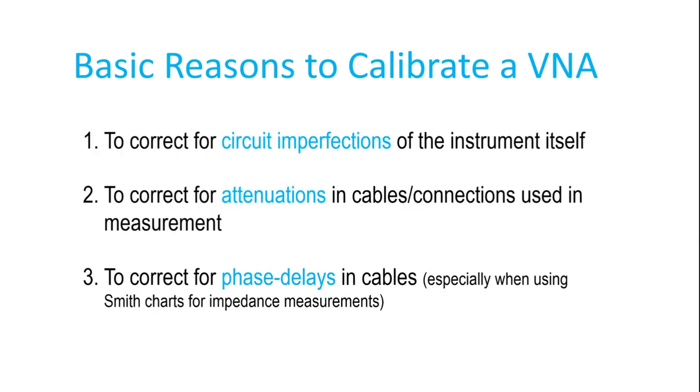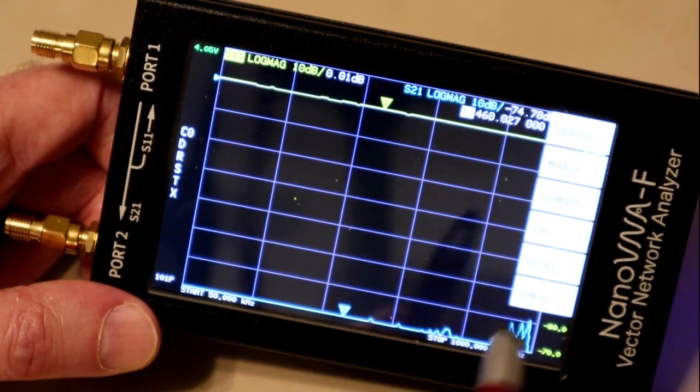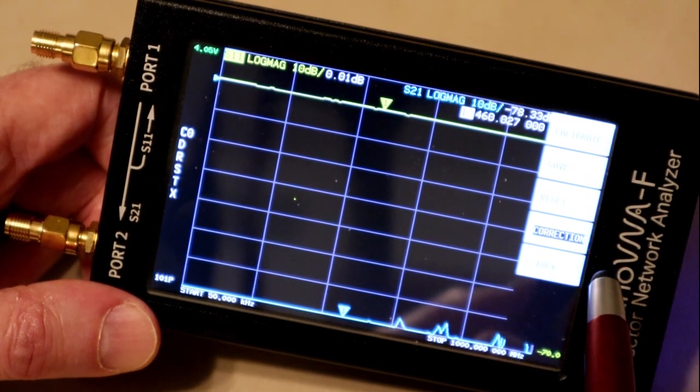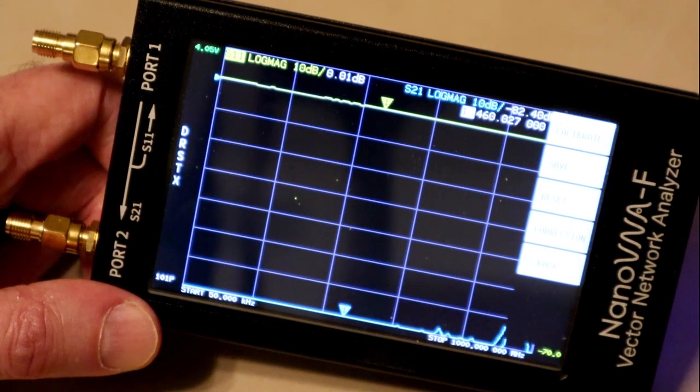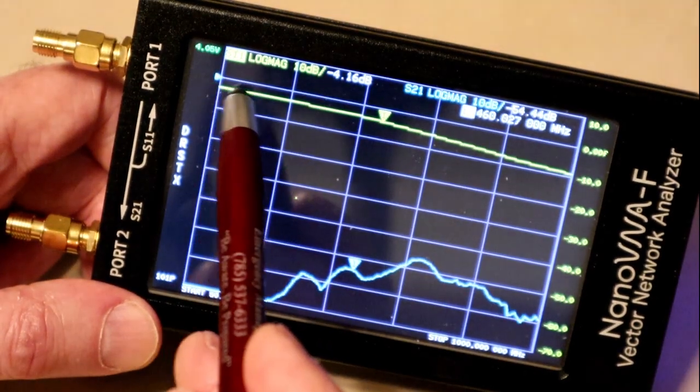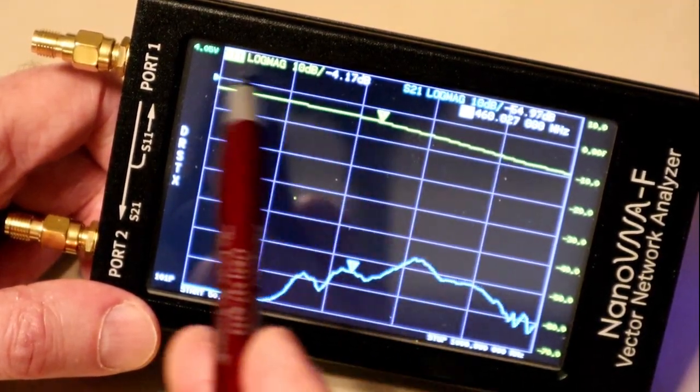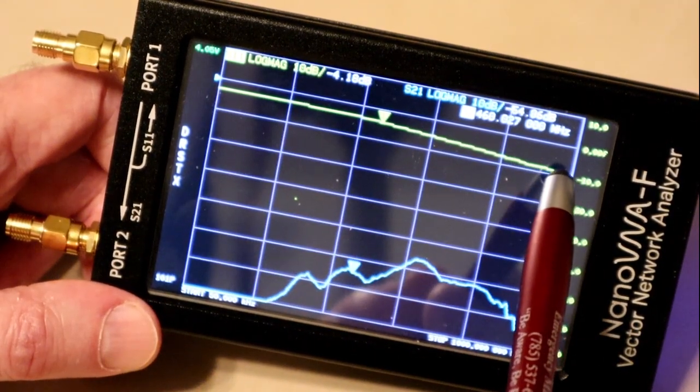So let's take a look at each one of these, starting with correcting for circuit imperfections. From the top level menu, I hit CAL, and it says correction, it's highlighted. I'm just going to hit it to turn it off. And now you can see what happened. At the low frequencies, we have a couple of dB drop from the 0 dB S11. At higher frequencies, we have even more drop.